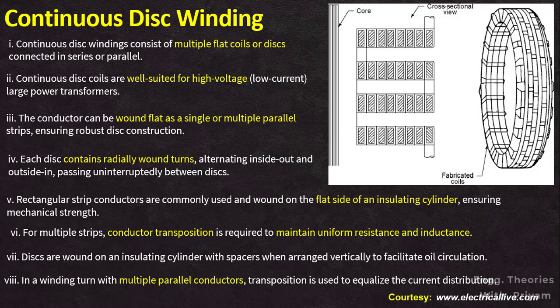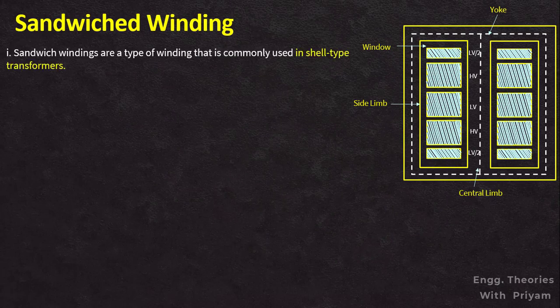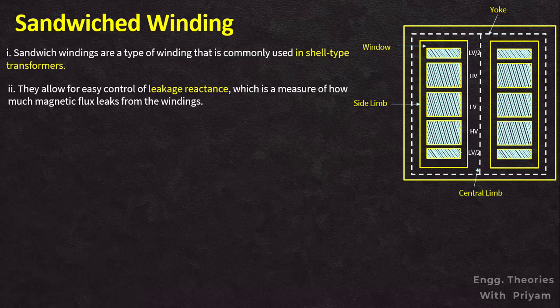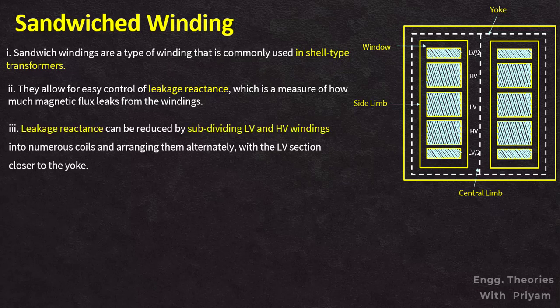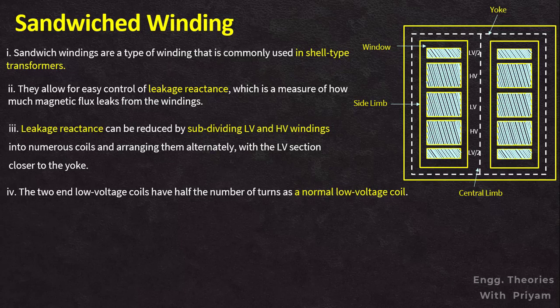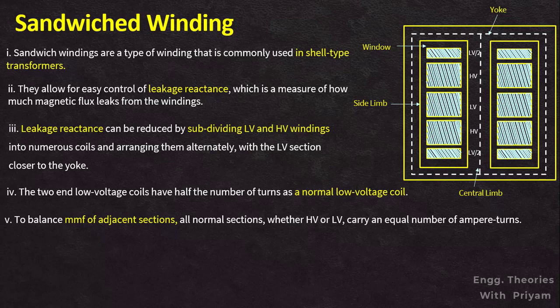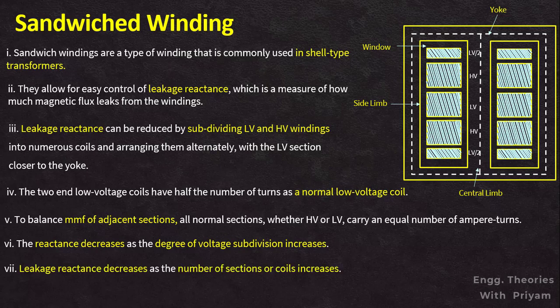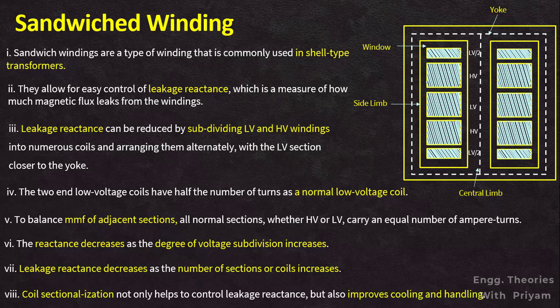Continuous disc windings are reliable and strong, making them a popular choice for both low voltage and high voltage windings in large transformers. Sandwich windings are commonly used in shell type transformers. They allow easy control of leakage reactance by dividing the LV and HV windings into a large number of sections, arranging HV and LV sections alternately with the LV sections closer to the yoke. The two end low voltage coils have half the number of turns of a normal low voltage coil. Each normal section — whether HV or LV — carries the same number of ampere-turns to balance MMF. Leakage reactance decreases as the number of sections increases, and coil sectionalization also improves cooling and handling.